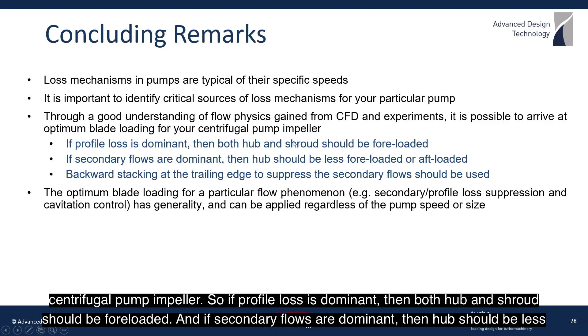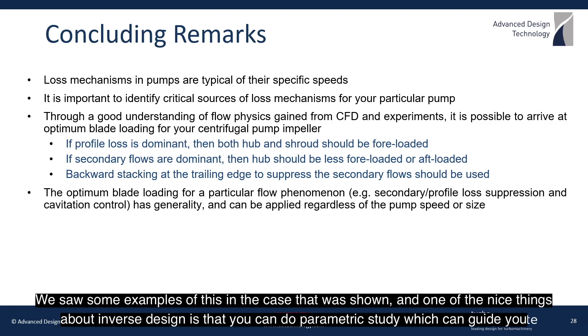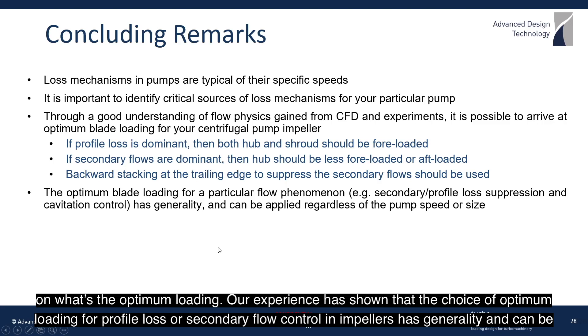If profile loss is dominant, then both hub and shroud should be fore-loaded. If secondary flows are dominant, then the hub should be less fore-loaded or even aft loaded compared to the shroud, and backward stacking at the trailing edge will help to suppress the secondary flows. We saw some examples of this in the case shown. One of the nice things about inverse design is you can do a parametric study, which can guide you on what's the optimum loading.